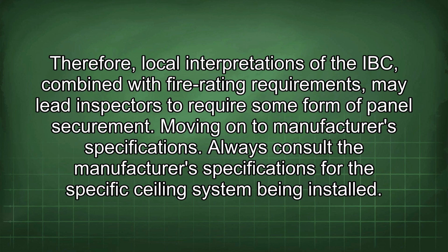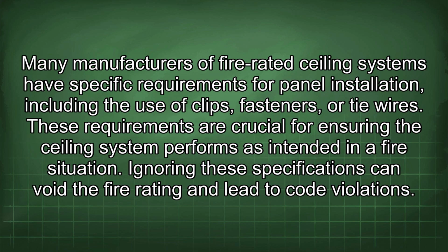Always consult the manufacturer's specifications for the specific ceiling system being installed. Many manufacturers of fire-rated ceiling systems have specific requirements for panel installation, including the use of clips, fasteners, or tie wires. These requirements are crucial for ensuring the ceiling system performs as intended in a fire situation. Ignoring these specifications can void the fire rating and lead to code violations.